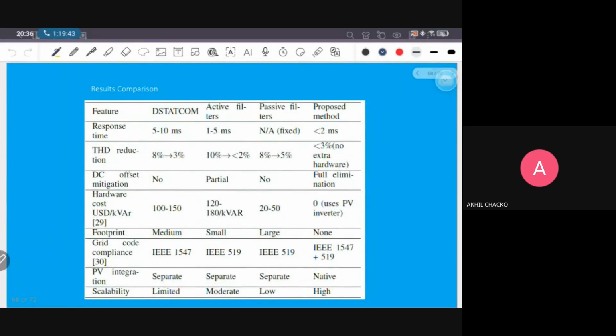So here we are comparing our results with DSTATCOM, active filters, and passive filters, and we get less than 2 millisecond reaction time with our proposed system. THD reduction is less than 3%, and DC offset is fully removed. Extra hardware cost is not required, but we have to limit the total reactive power compensation and harmonic power compensation within the rating of the inverter.